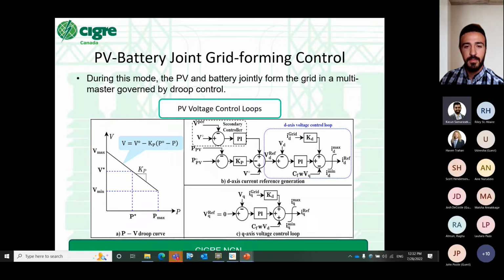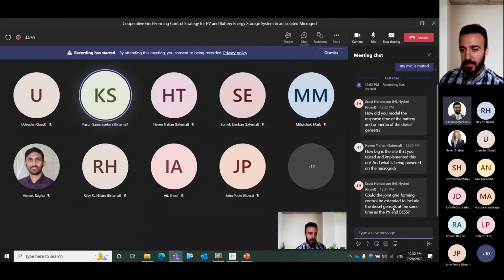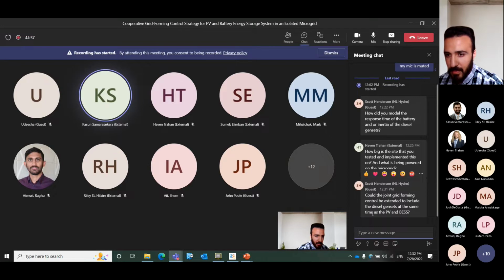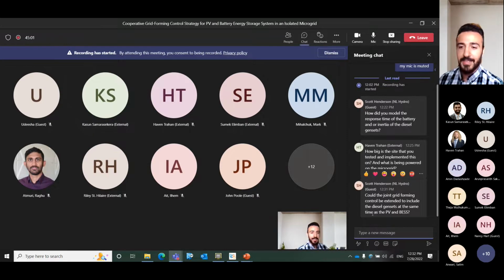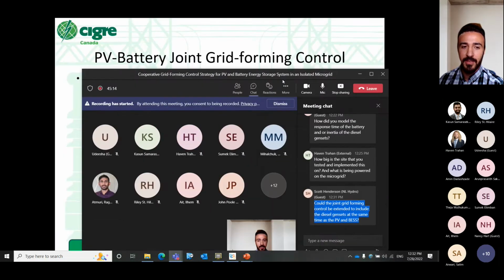We got a question in the chat from Scott Henderson. Could the joint grid forming control be extended to include the diesel genset at the same time as the PV and battery energy storage? That's very interesting, actually. I haven't tried that, but I will try to do so. I haven't tried to include the genset into the droop mode with the PV and battery actually.